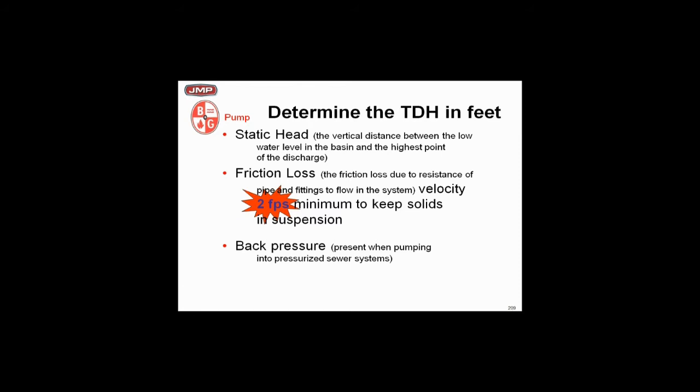We also got friction loss through the pipe to calculate the pump head, and we got to make sure the velocity stays over two feet per second to keep these solids entrained and moving. We also may have back pressure where we're pumping to pressurized sewers or they're going up a hill and you have back pressure.